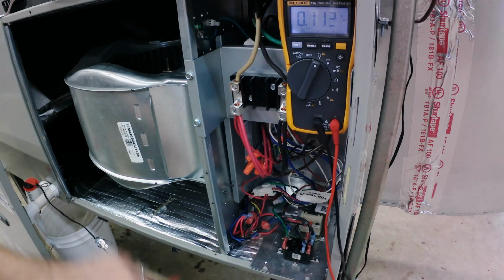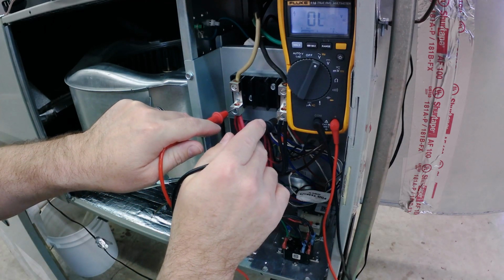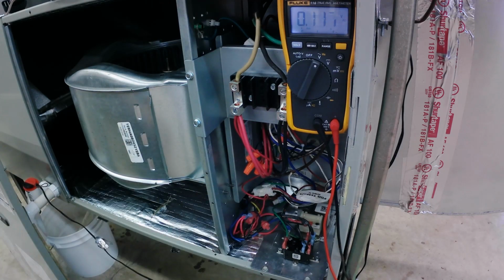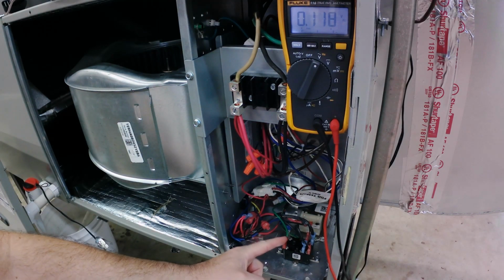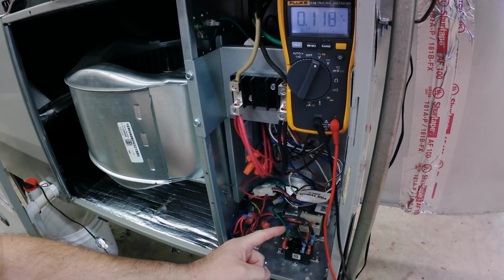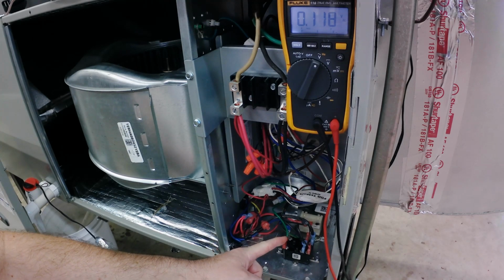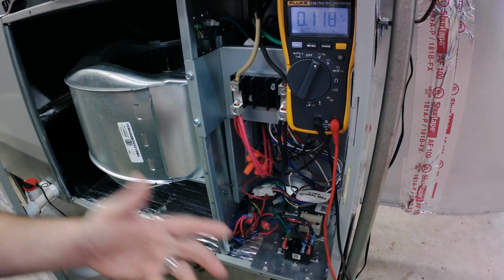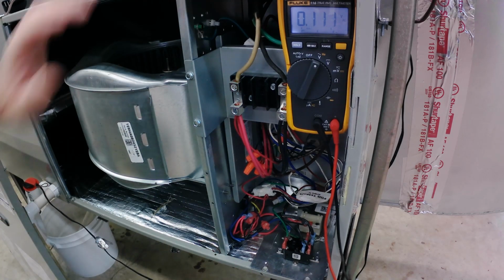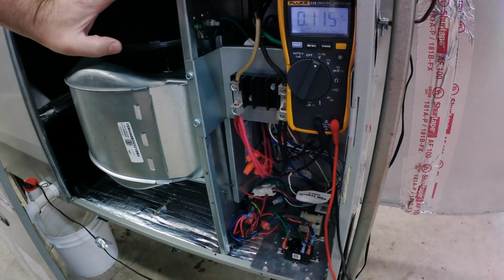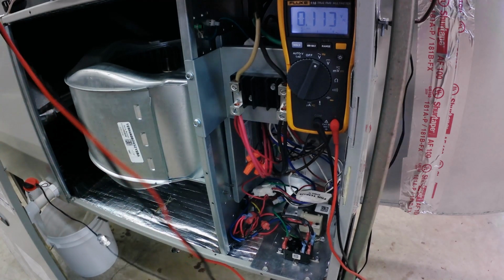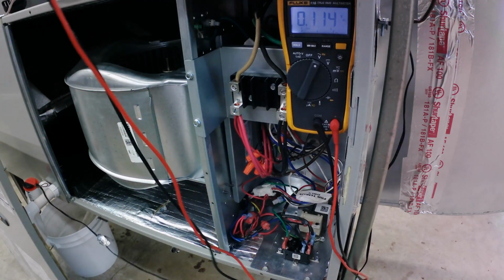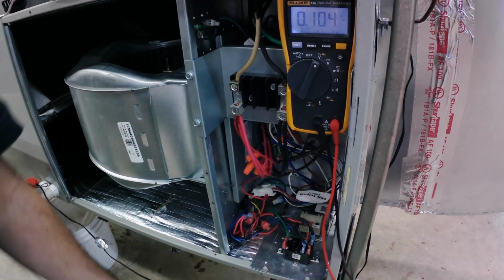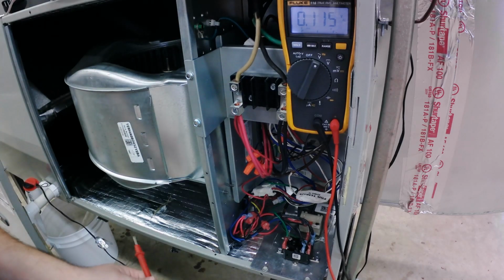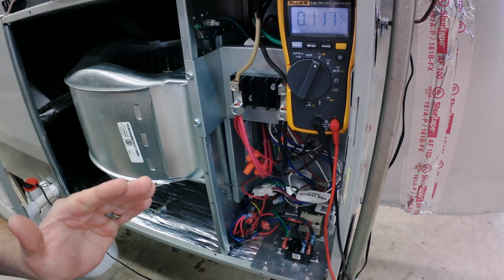Now, once I prove power or something like that, and you can even check 24 volts at the transformer secondary if you want. But as far as I'm concerned right now, this relay is not turning on the fan because it hasn't been told to by the thermostat. Now, I'm going to reach up here and turn the thermostat on. So I just turned on the fan from auto to on.